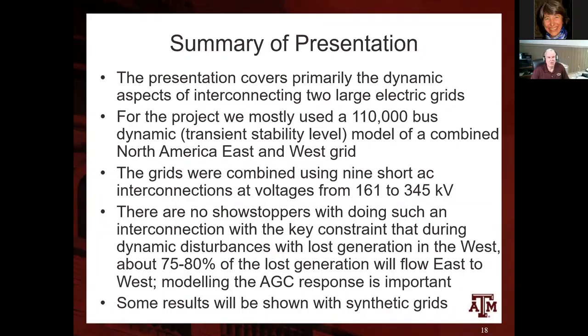We looked at different locations where the grids are naturally close, and in consultation with the utilities helping us, we connected them. There were 9 short AC interconnections at voltages between 161 and 345 kV. Sometimes the connections were very simple, such as at the Laramie River generator, where the east and west are actually both right there, and we just had to close a bus tiebreaker to connect them. Other places required a transformer or a short transmission line.